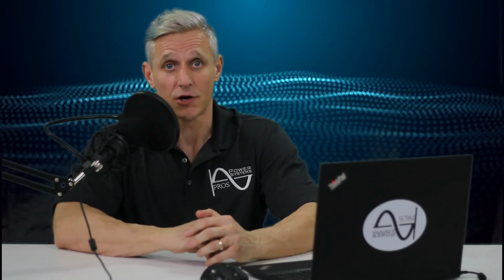are arc rated. Arc rating is a value attributed to materials that describes their performance to an exposure to an electrical arc flash occurrence. The arc rating is expressed in calories per centimeter squared, and it's actually derived from the determined value of the arc thermal performance value, or the ATPV, or energy of the break open threshold, EBT, should a material system exhibit a break open response below the ATPV value. Arc rating is reported as either ATPV or EBT, whichever is the lower value.